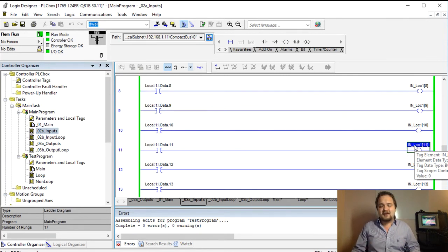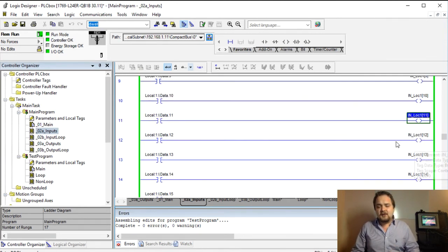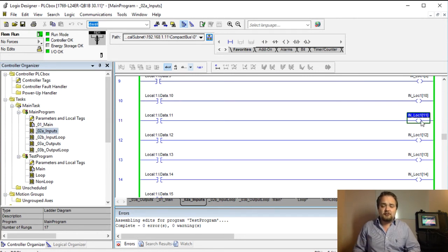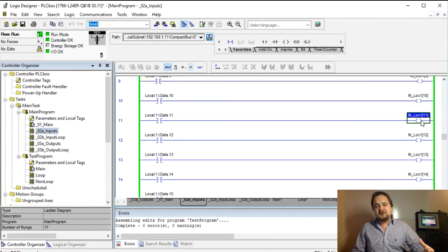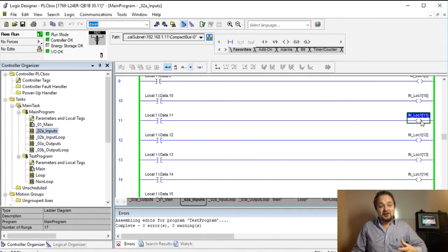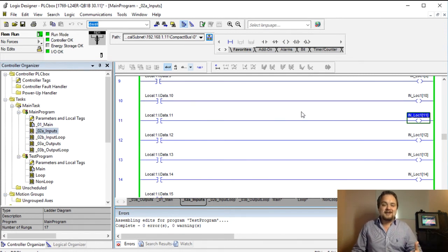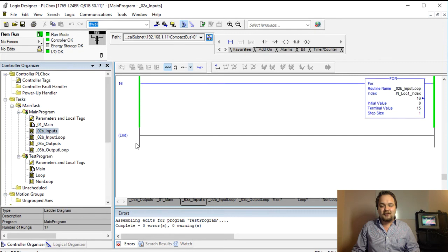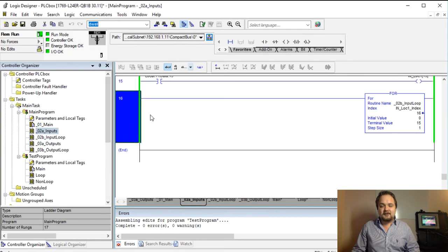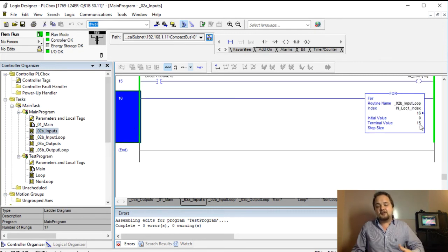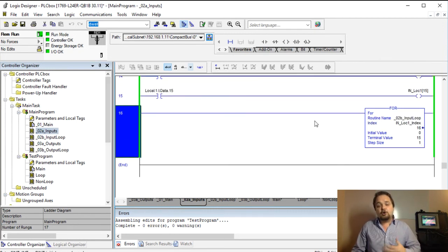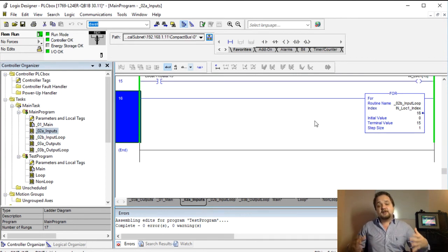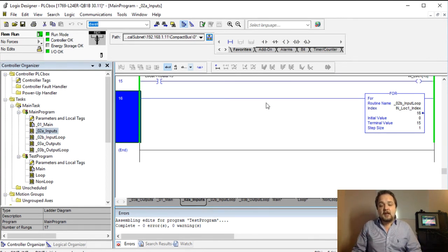And I want to do that very systematically I don't want to essentially create a loop around this and then add a timer and then add another bit which is being energized and I want to have a delay off for my bit for example on the input side as well so what I've created here is up all the way at the end I have this loop function which essentially cycles through the 16 inputs currently present on the PLC and of course I'm going to expand the system and it's going to have a lot more inputs and all I need to do is essentially just expand this index to a lot more to accommodate a lot more inputs.